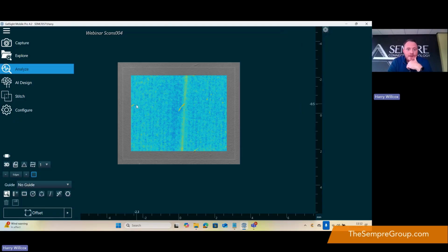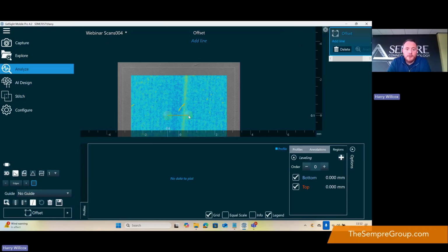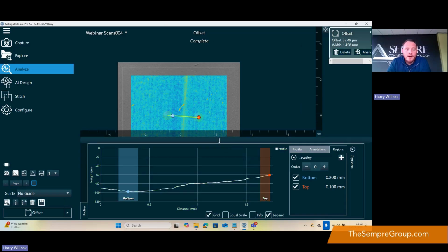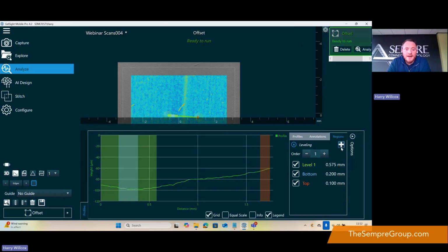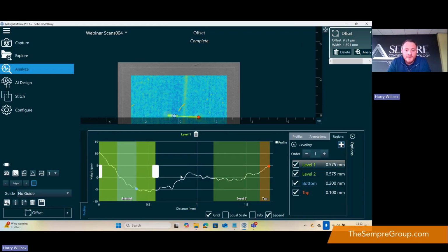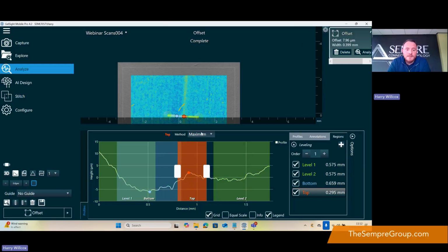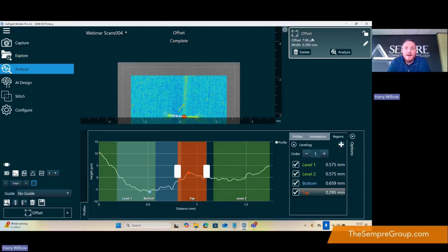You can see we picked up these defects that are on the surface, or they're positive, so it's debris. But then I've also got this line going through the center, which is where our machining mismatch is. What I can do is use one of the tools in the software, draw a profile across it, and we can see the mismatch in the material. If I level one of the sides, level the other, we can see this step change. To measure that mismatch, I can go to the minimum here, and I'm going to find the peak of this surface as a maximum. And you can see there's a 7.96 micron mismatch in the material.